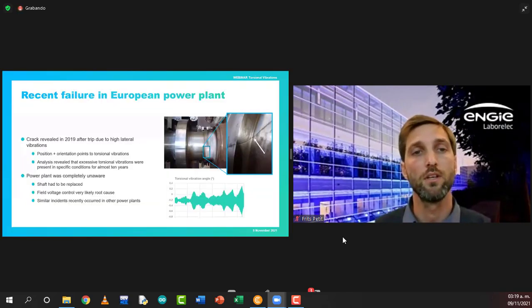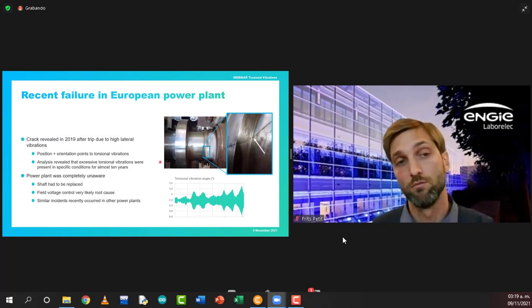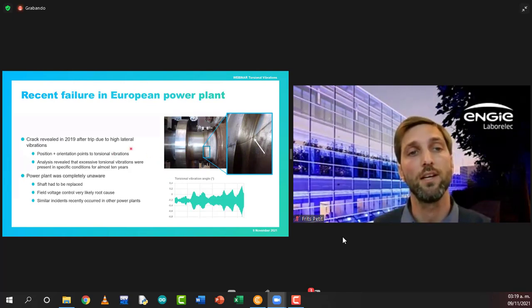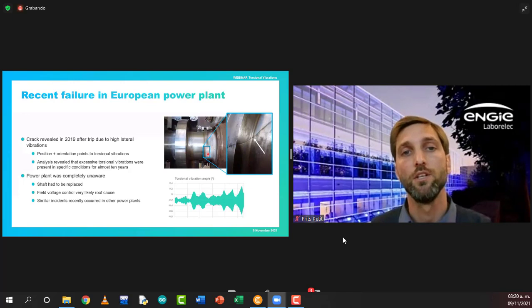The first one is a very recent one, 2019, where we experienced a large crack in a compressor rotor shaft, actually near the coupling between the compressor rotor shaft and the HIP steam turbine. You can see here the crack appeared in a fillet, in a stress concentration on the shaft, and the shaft had to be replaced. There was an unavailability of almost 1 year due to the replacement of the shaft.